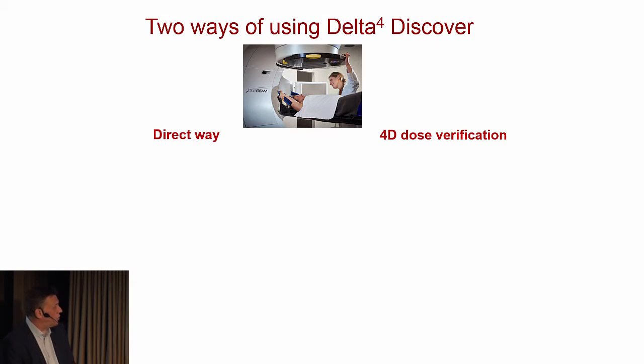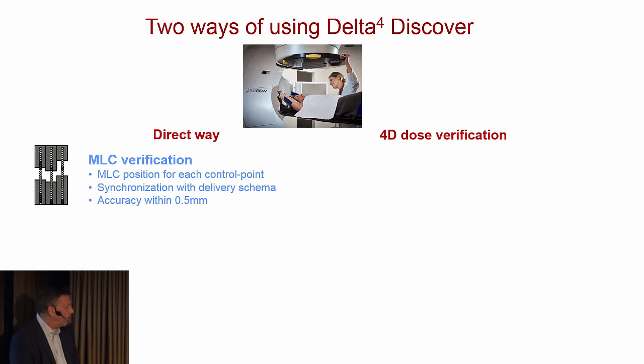The Delta4 Discover has two ways of measuring the dose distribution. It has the direct way, and it has the 4D dose verification way. The direct way is a faster way of doing it, and the 4D dose verification is the outstanding quality way of doing it. The direct way includes MLC verification. So the MLC leaf positioning per control point is verified, and it is verified with a very good accuracy, better than 0.5 millimeter per control point. That's extremely good. And it's completely synchronized with the delivery of the treatment. Of course, it's extremely important that we have synchronization with the delivery, because if you don't have the synchronization, you don't have anything to compare with. And therefore, it's extremely important to have this information as well.